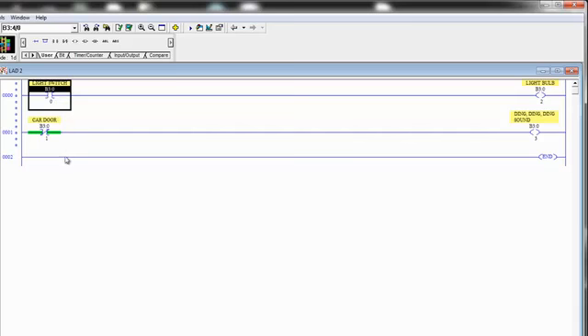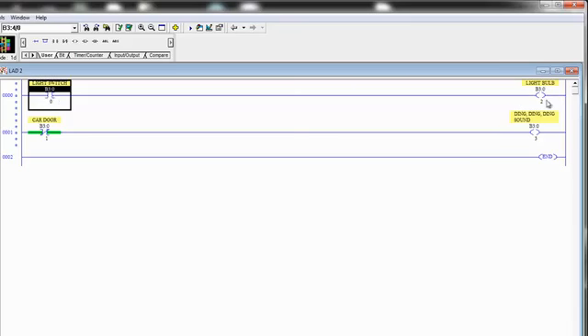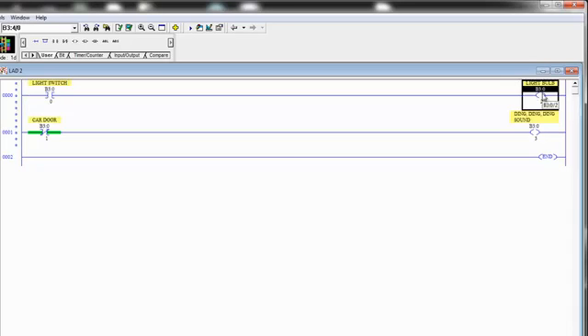So I will tell the program by putting blocks like this in there, check B300 to see if it's open or to see if it's closed. And depending, maybe we'll do an instruction to the right, maybe we won't. In this case, if B300 is closed, we want to go ahead and energize an output. And of course, we're going to have that address, B302, we're going to have that tied to an output, namely our light bulb.